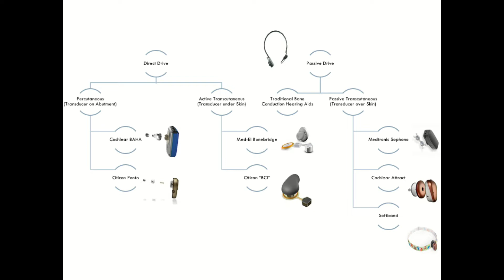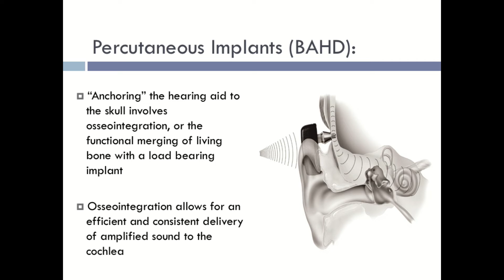We are eagerly anticipating this active transcutaneous system that is not really out yet on the market, but soon will be, where that sound generator, the oscillator, is embedded in the bone already. So it's that much closer to the cochlea, and that will improve, we believe, the cosmetic aspect of this device and cut down on obviously the skin issues you won't have in an open wound around an abutment anymore. But for now, we're relying on the gold standard, and that system that involves the titanium screw here is effective because the bone essentially grows around that screw and becomes part of the skull. So the sound transmission is extremely efficient. We don't have to drive the device as hard throughout the day.